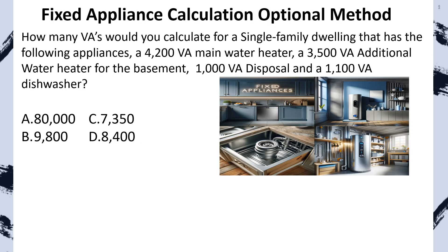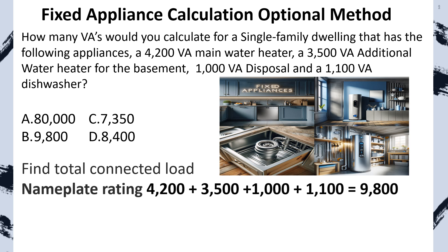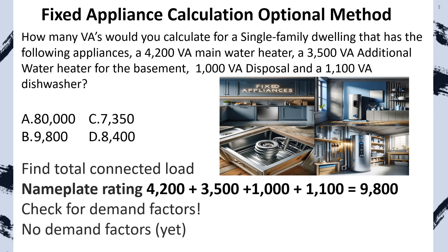How many VAs would you calculate for a single family dwelling with the following appliances: a 4,200 VA main water heater, a 3,500 VA additional water heater for the basement, a 1,000 VA disposal, and a 1,100 VA dishwasher? First, find the total connected load. With the optional method we take the nameplate rating of all these appliances. There are no demand factors yet at this portion of the calculation — all we do is total up all these appliances, then we'll apply one general demand factor in just a little bit. The answer is B.